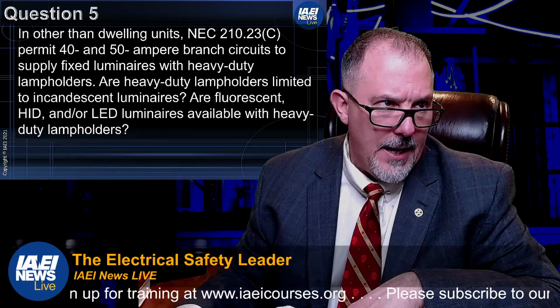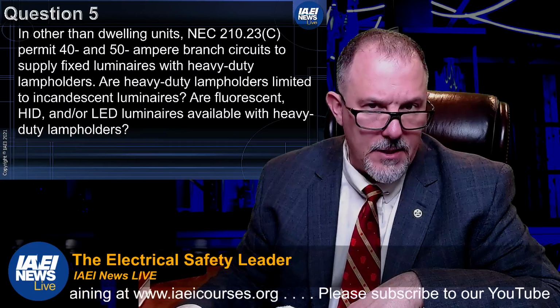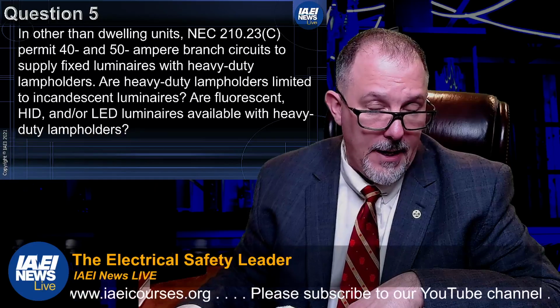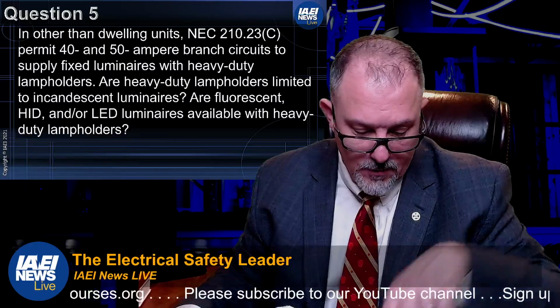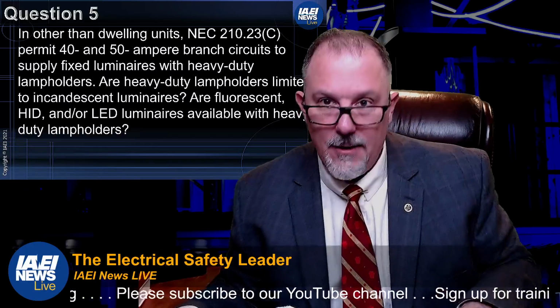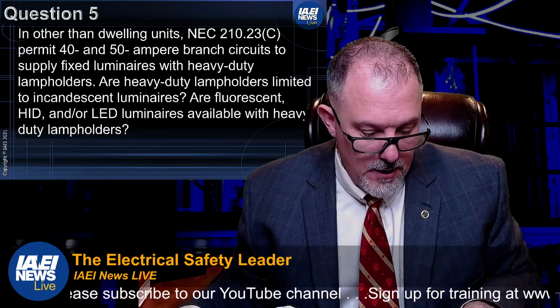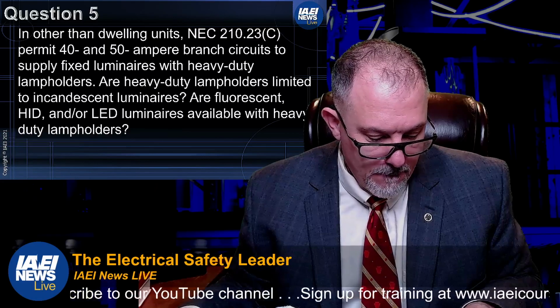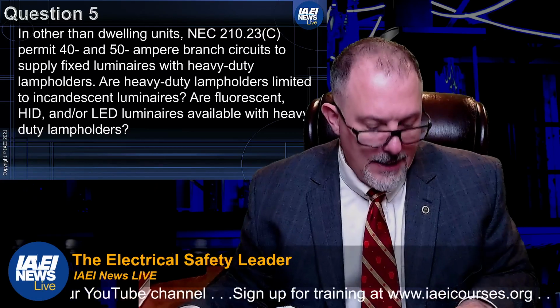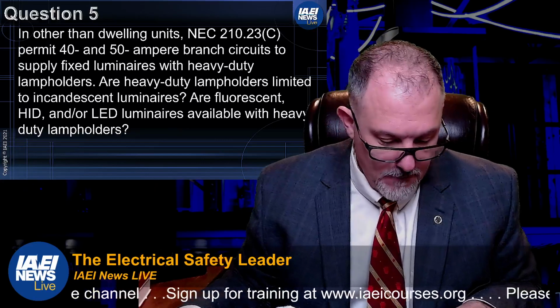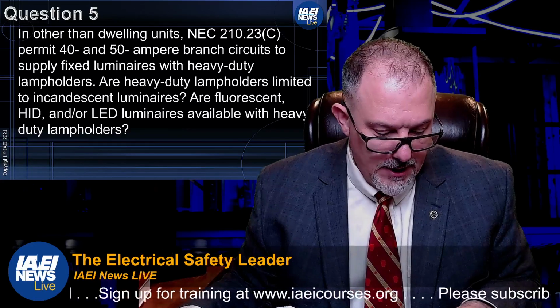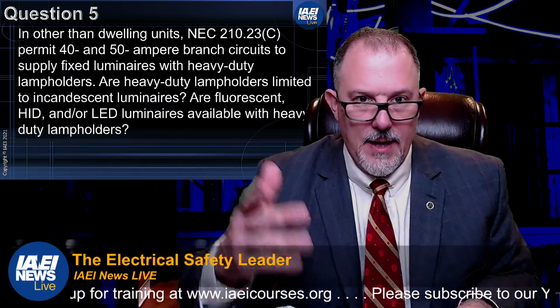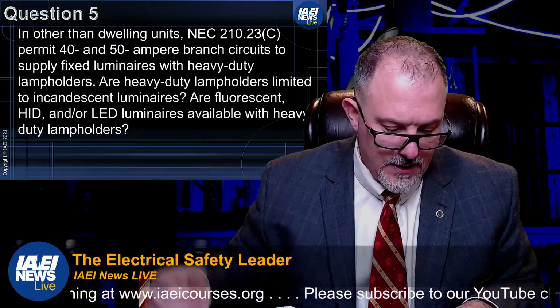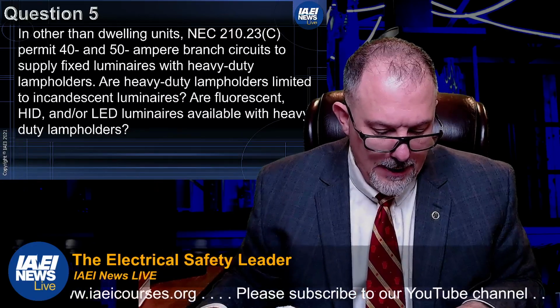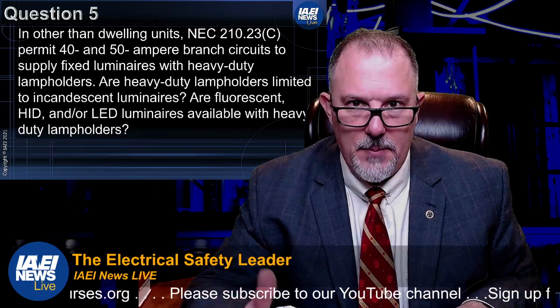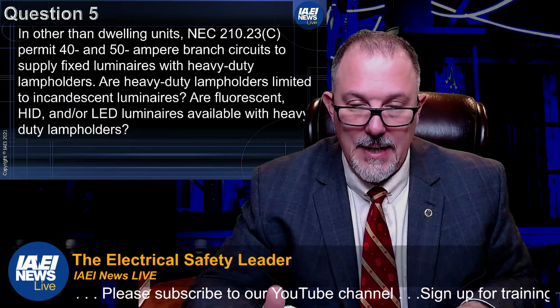Let's take a look at 210.21(A). 210.21 is outlet devices. A is lamp holders. Where connected to a branch circuit having a rating in excess of 20 amps, and 40 and 50 would be in excess of 20 amps, it tells us that the lamp holders have to be of the heavy-duty type.